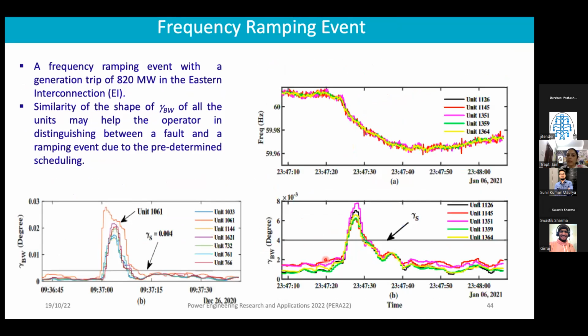But one more important thing which we identified was that sometimes a frequency ramping event is happening, which is because of some schedule changes in the system. That should not be confused with an event. So how do we distinguish this? We identified this from the Eastern interconnection. These are the frequency measurements, and when we computed the variability of the big window, it was found to cross the threshold. But then how to distinguish it? Its shape will indicate whether it is an intentional event or a frequency ramping event. Because all the units have a similar kind of shape, it tells you that it is due to scheduled or planned scheduling. So this similarity of the shape of the variability of the big window across all the units may help the operator in distinguishing between a fault and a ramping event due to predetermined scheduling.